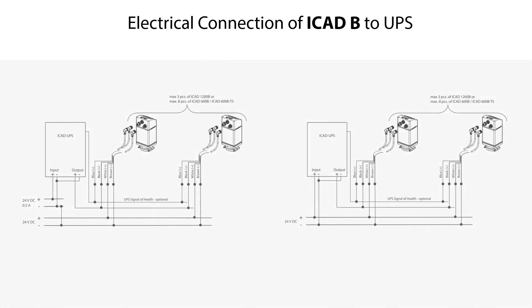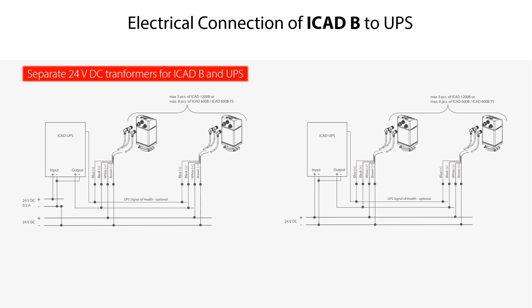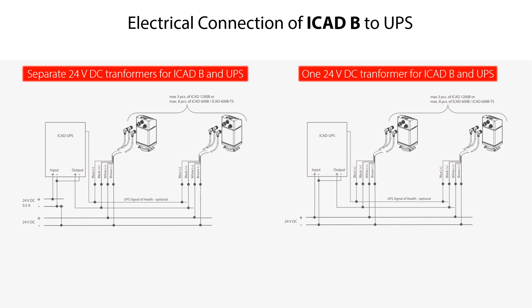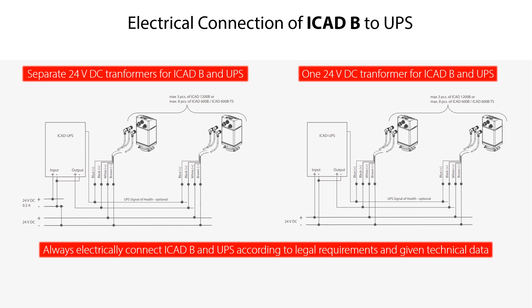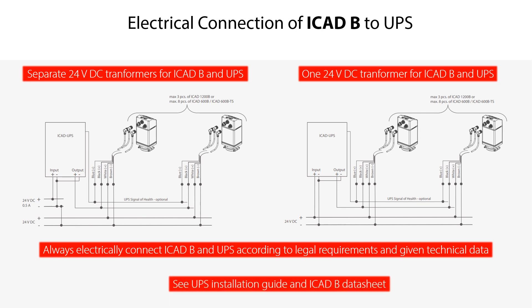Here you see two options of how to electrically connect the ICAD-B to the UPS: with separate 24-volt DC transformers for the ICAD-B and the UPS, or with one common 24-volt DC transformer for both the ICAD-B and the UPS. You should always electrically connect the ICAD-B and the UPS according to legal requirements and the given technical data. You can find more information in the UPS installation guide and the ICAD-B data sheet.